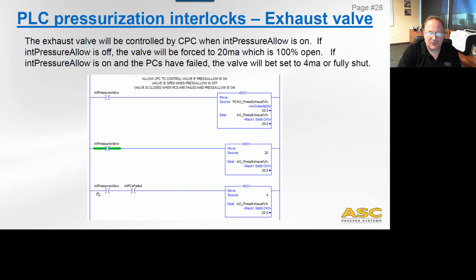And here's another case where there are three conditions now. There's one that leaves it wide open, and then one that closes it. The reason I'm doing that is because I don't want to move the exhaust valve to full open when the PCs fail, because that will end the run and destroy the parts. And normally we want to put it in a closed condition, giving the operator enough time to reboot the computers and try to figure out what's wrong with the PCs.